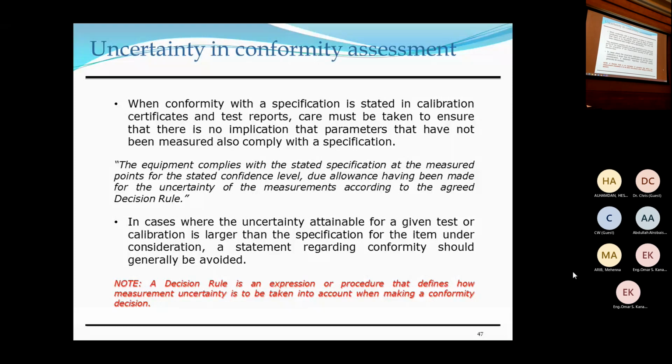Yes, you need to have a procedure for how you use uncertainty to decide conformity. There's information regarding this. You can find it in ILAC G8. So ILAC G8 has all of the necessary information for you to write such a procedure.